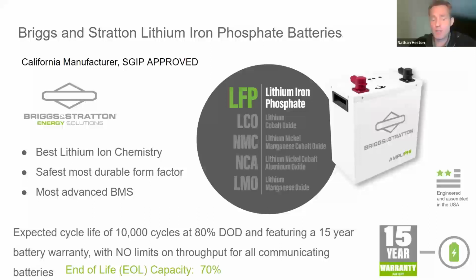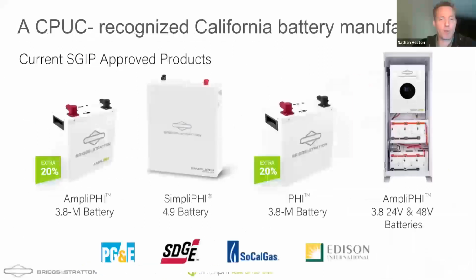We still allow 100% depth of discharge. We recommend 80% because at 100% depth of discharge, we're looking at 3,500 cycles on the battery. But with 80% depth of discharge, we're expecting 10,000 cycles. So you do get a big jump there. If you do a 90% depth of discharge, it's more like 6,000 cycles. And we still expect an end-of-life capacity of 70%. I don't think there's any company out there that can offer better expectations for life cycle of their batteries and back it up with a warranty from a company that's going to be around. We've been around for 115 years. Briggs & Stratton will be there to back up their warranty.